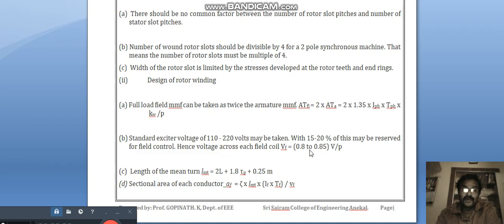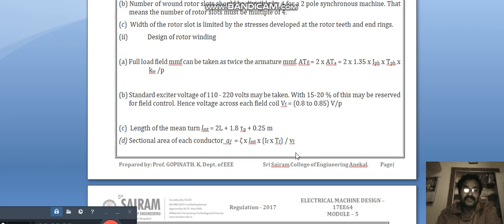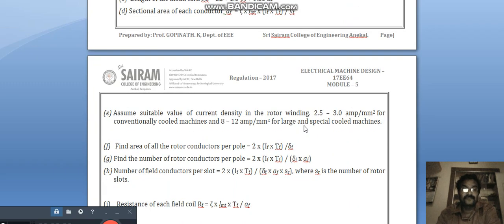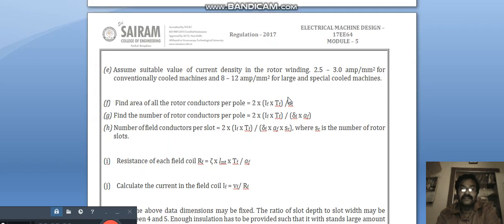Hence voltage across each field coil V_f is equal to 0.8 to 0.85 V per pole. Length of the mean turn LMT is equal to 2L + 1.8τ_p + 0.25 m. Sectional area of each conductor A_f is equal to ρ × LMT × I_f × T_f / V_f. Assume suitable value of current density in the rotor winding: 2.5 to 3 amp per mm² for conventionally cooled machines and 8 to 12 amp per mm² for large and special cooled machines.